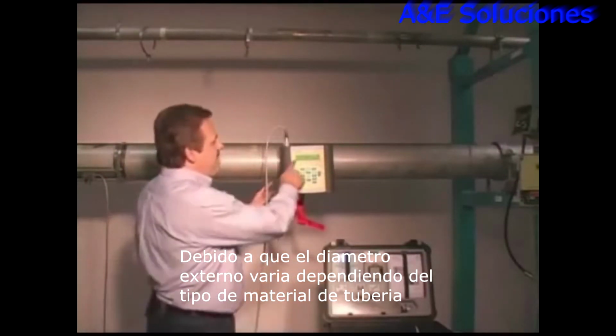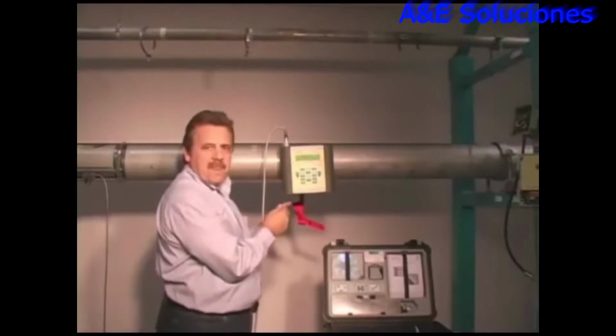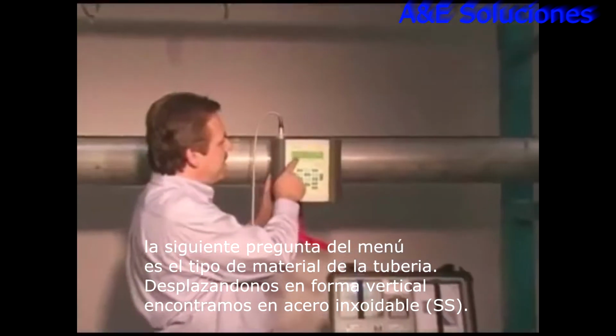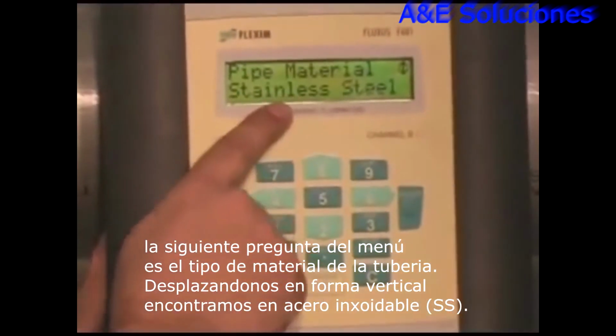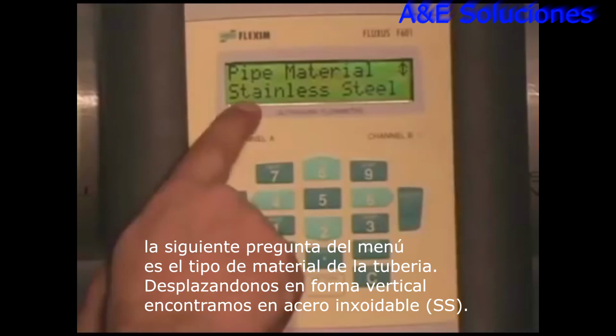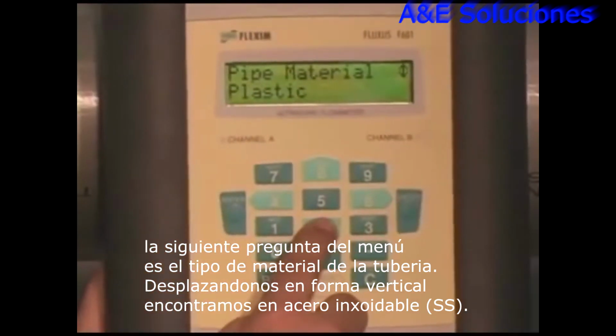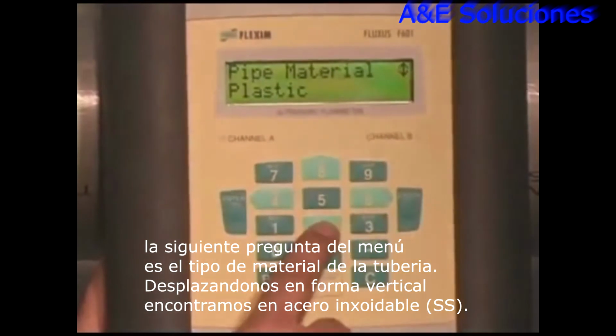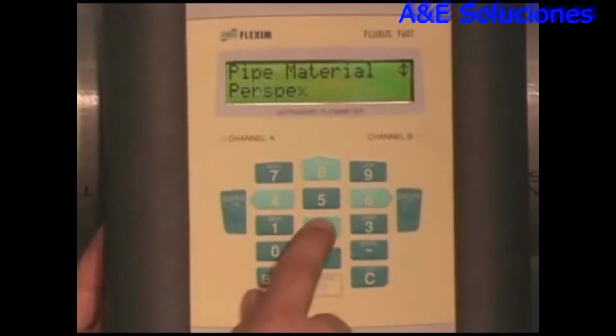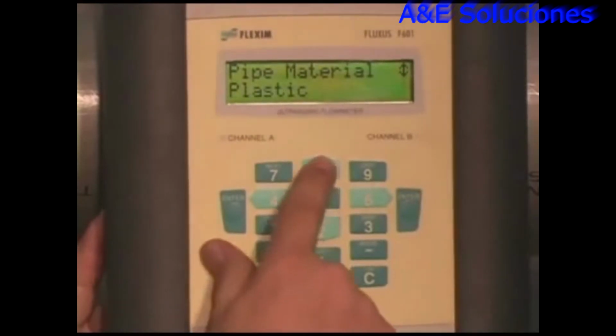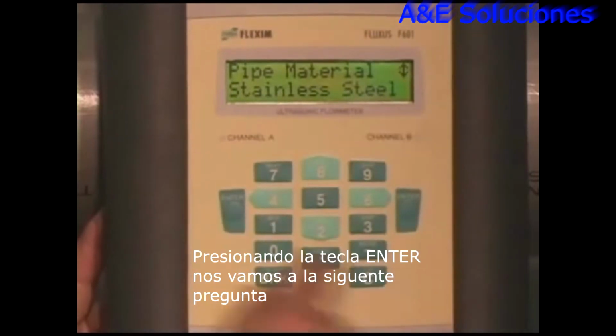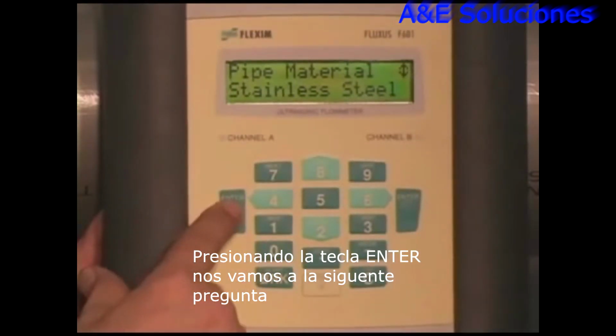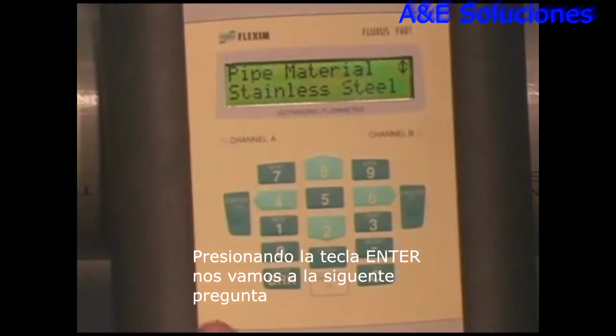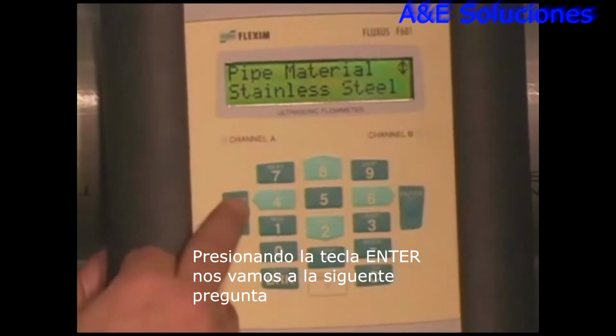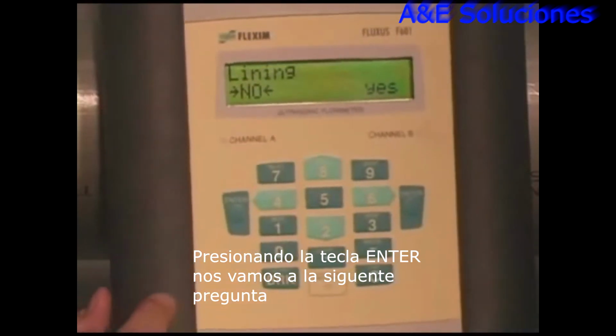Okay, so I've measured, I've installed the pipe outside diameter, I've installed the wall thickness, and the next question the meter asked me is, what's the pipe material? And here we've selected stainless. You'll see I have the little up down arrow prompt here, so if I scroll through you'll see there's quite a list of virtually any pipe that you're going to come across. There's the stainless again. Okay, so we'll stop on the stainless and hit enter. Now, if the material or the entry that you're looking for is already present, you just hit the enter key. And that moves you to the next question.